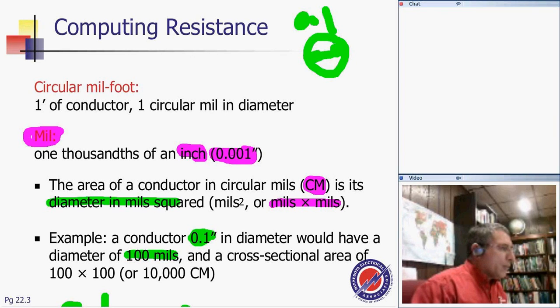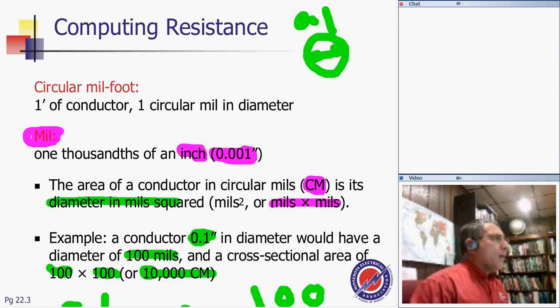Think of it this way: I know that's what the mil is. So how do you make 0.1 into 100? As you can see, this is 100, basically by multiplying by 1,000. So that's 100 mils. If you take 100 mils and you square it, take 100 times 100, that will give you 10,000 circular mils.